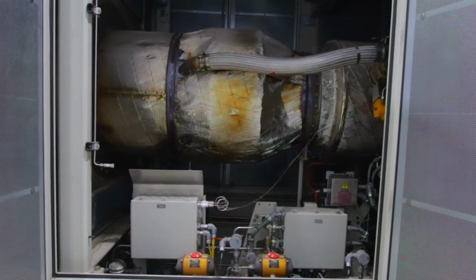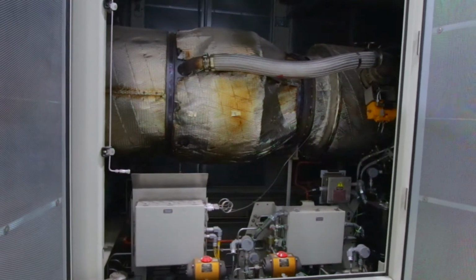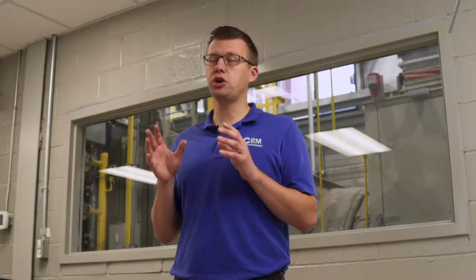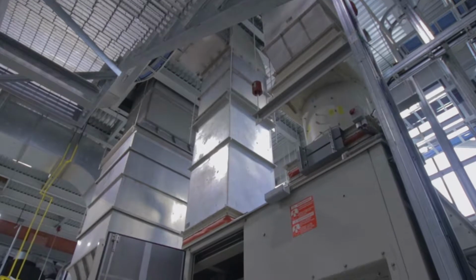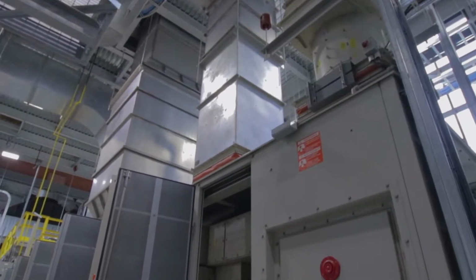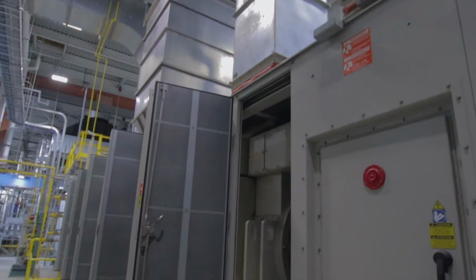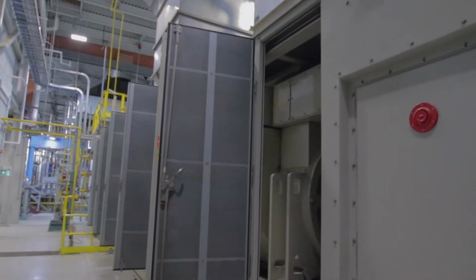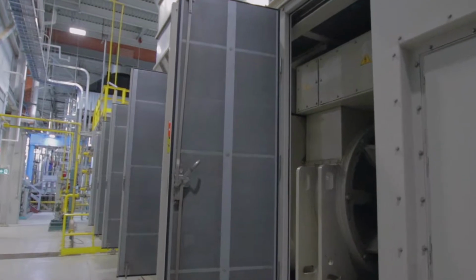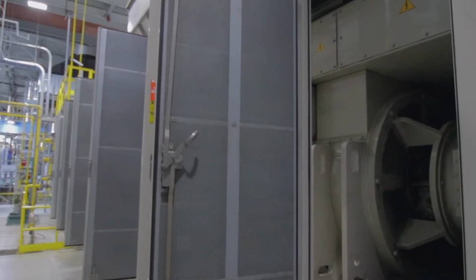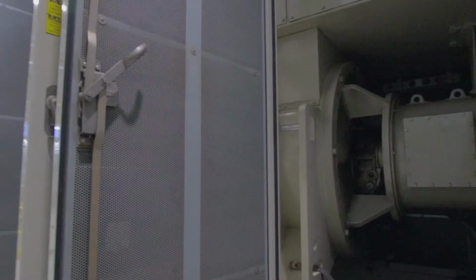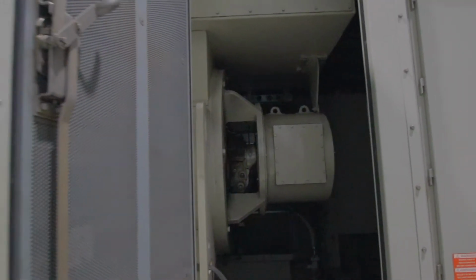A gas turbine like the one here at Campbell's is really well suited for anybody with a large heat load in various different forms. So whether they need a lot of steam, whether they need a lot of chilled water year-round, whether they need a lot of hot air for drying processes, anybody who needs a lot of energy, who's currently consuming a lot of natural gas to do their process is a good fit. In addition, plants or facilities or campuses that have a continuous electrical load anywhere between 3 megawatts and 5 megawatts, this is also a nice fit electrically. So we want to find sites that have that balance of both electrical needs between 3 and 5 megawatts and then thermal needs that are pretty sizable.